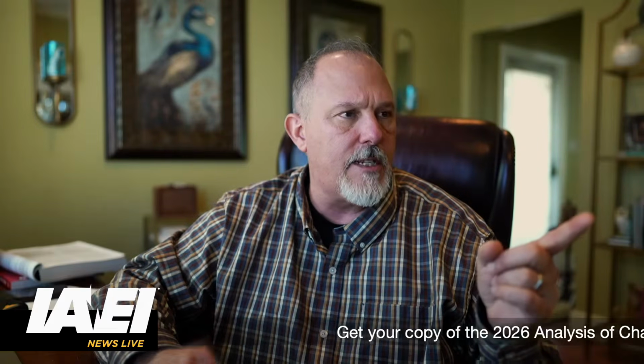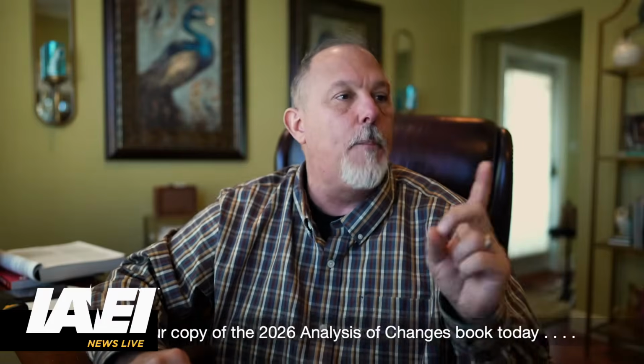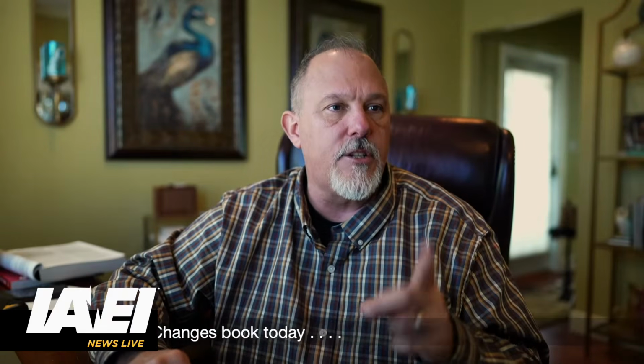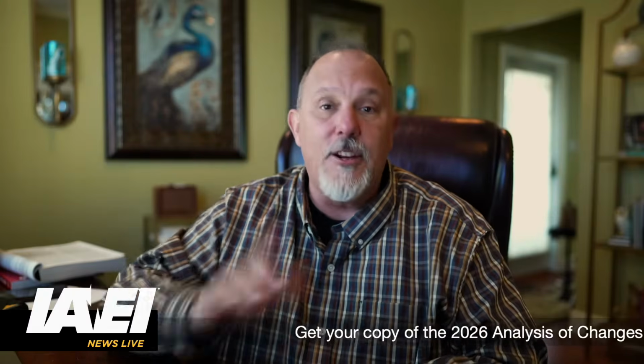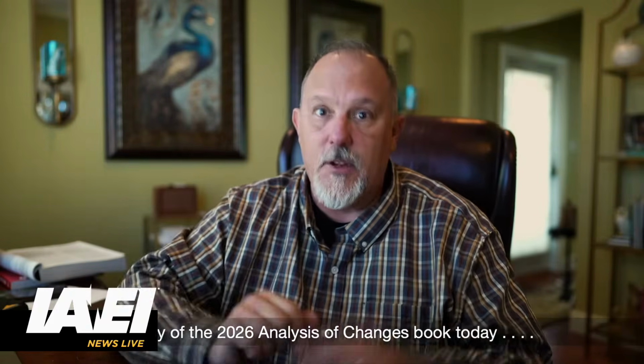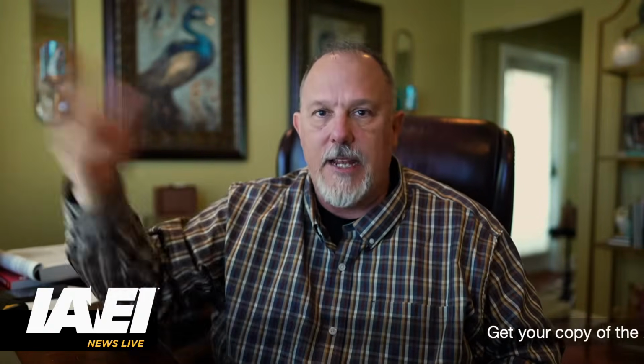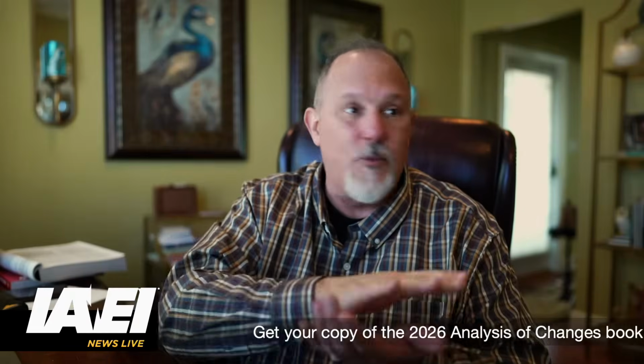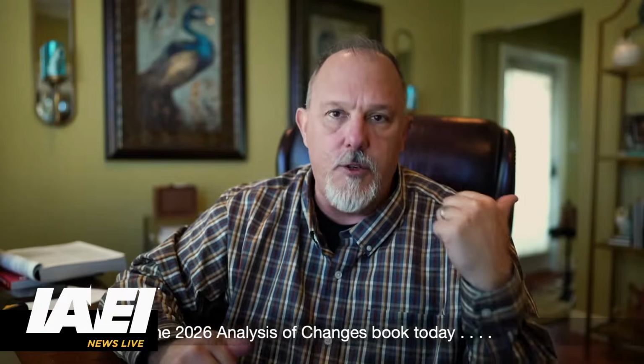And what it said was, in other than dwelling units, in addition to the requirements in 110.16(A), which is that there's a hazard, a permanent arc flash label shall be field or factory applied to service equipment and feeder supplied equipment rated 1,000 amps or more. And it said the arc flash label should be in accordance with applicable industry practice and include the date that the label was applied, not when it was created, because I could create it today and it won't be applied until a few days later. We fixed that too, so it's when it was applied. We'll take a look at the new 110.16 language. And it said that the label has to meet the requirements of 110.21(B).